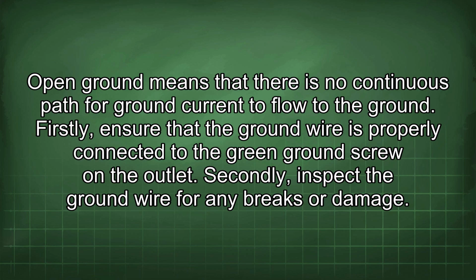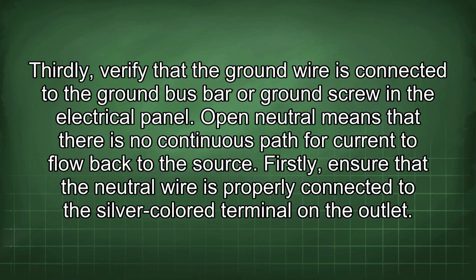Firstly, ensure that the ground wire is properly connected to the green ground screw on the outlet. Secondly, inspect the ground wire for any breaks or damage. Thirdly, verify that the ground wire is connected to the ground bus bar or ground screw in the electrical panel.